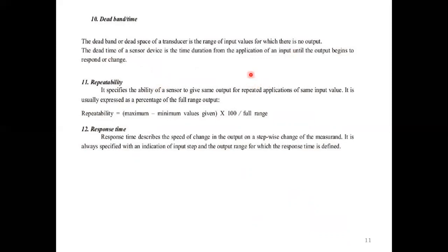Next one, repeatability. It specifies the ability of a sensor to give the same output for repeated applications of the same input values. It is usually expressed as a percentage of the full scale range output. That means repeatability is equal to maximum minus minimum values given, multiplied by 100, divided by full range. That is repeatability.